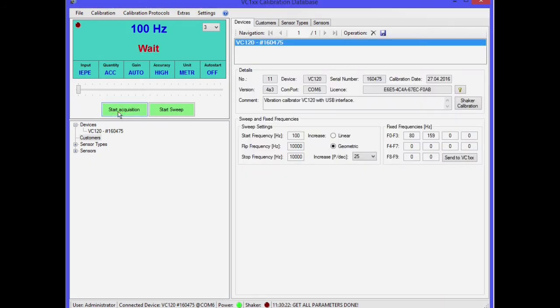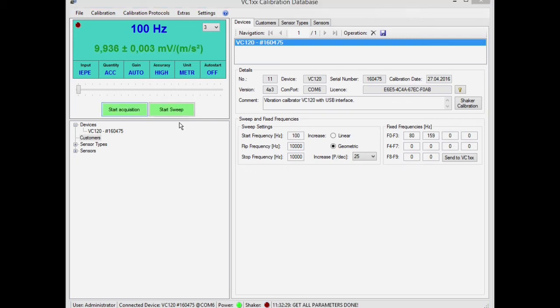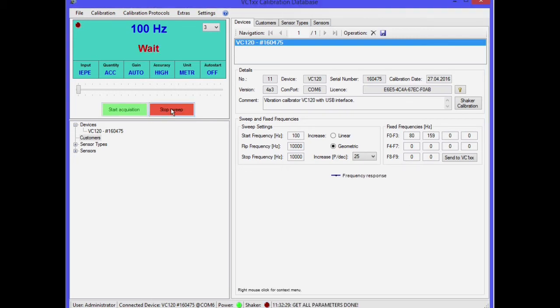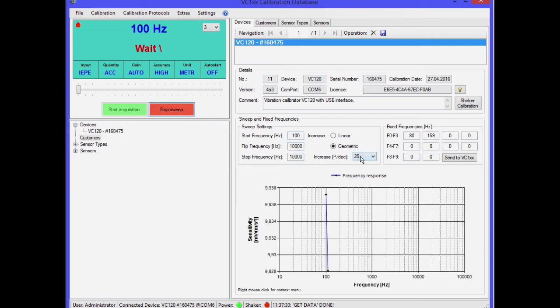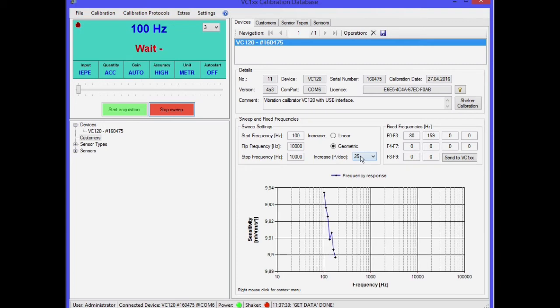Click on Start Acquisition to start a manual calibration. The recorded sensitivity will appear on the screen. By pressing Start Sweep, you can record a frequency response graph. You can edit parameters such as start and stop frequency or frequency increment. Click on the diagram to select axis scaling or export options.